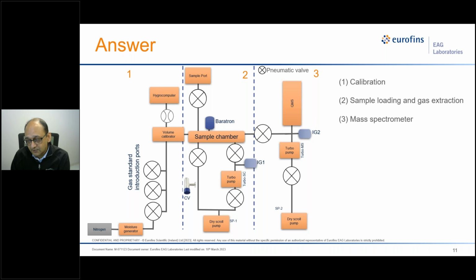Now let's move to section 2, where the heart of the entire system is the sample chamber. It is connected to the sample port, and another one is the volume calibrator, as we talked about, and it has an independent Baratron, which is a capacitance manometer pressure gauge system, to measure the gas pressure inside the sample chamber. Beneath the sample chamber, we have two valves which isolate the vacuum generation arrangement. So we have a turbo pump and a bypass line that goes to a dry scroll pump, which is nothing but a scroll pump without any oil or any kind of contaminant, and that supports the bypass line as well as the turbo pump. We have a unit called IG1, which is an ion gauge that measures pressure in the range of 10 to the power minus 8, minus 9 torr. So that's the function of section 2.